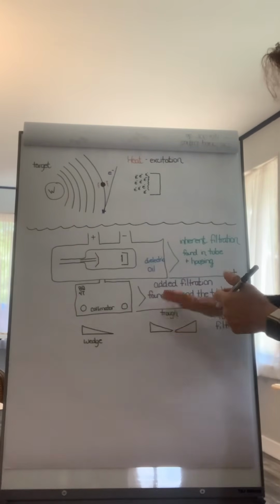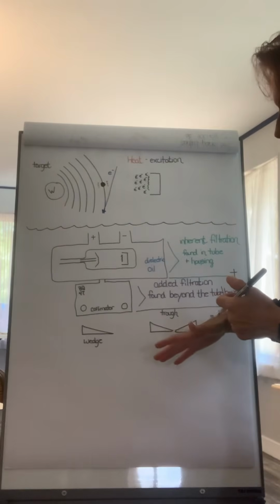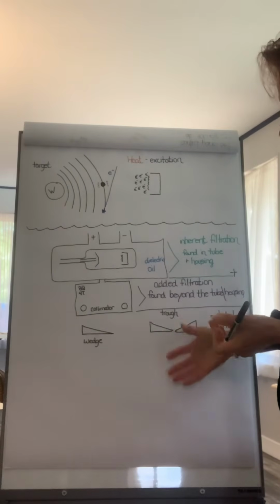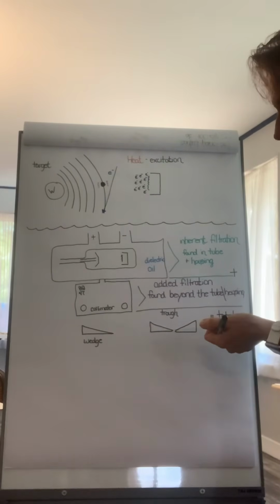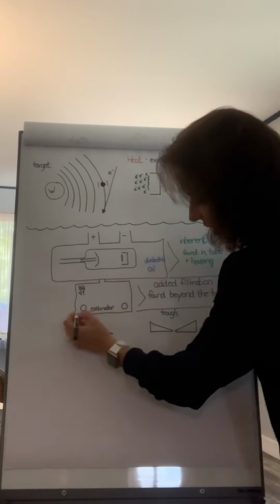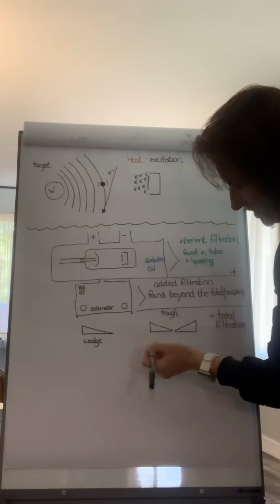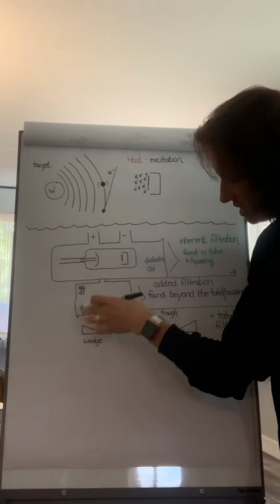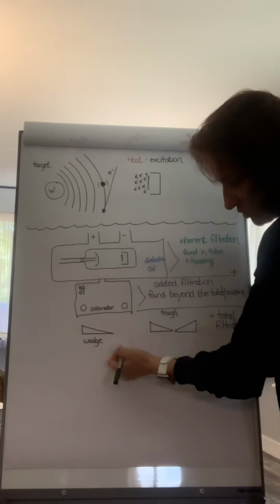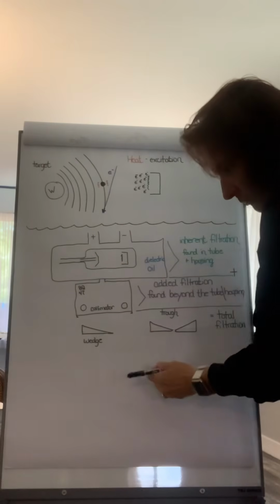Okay, and then there's also things that they talk about, compensating filters that you can add to the bottom of the collimator. Usually it'll have little tracks like this, kind of like on a stove, how you put the racks in, and then you slide the filter into that. They gave an example of a wedge filter.